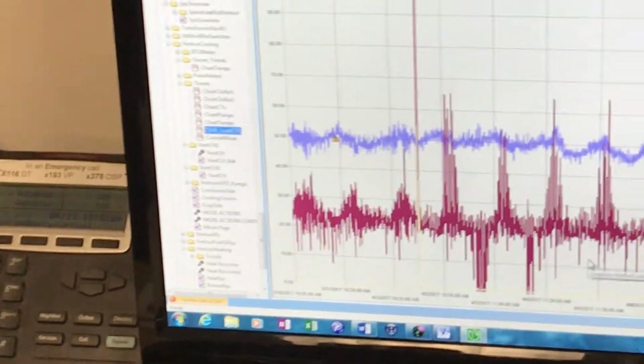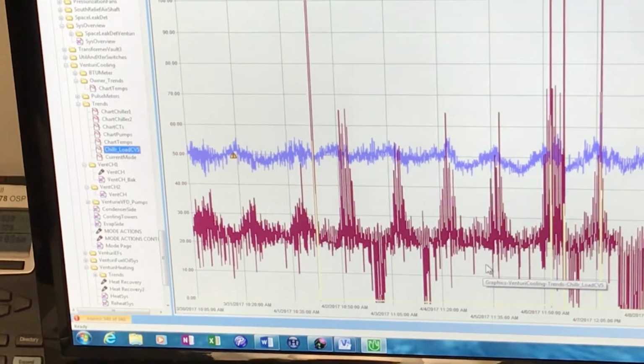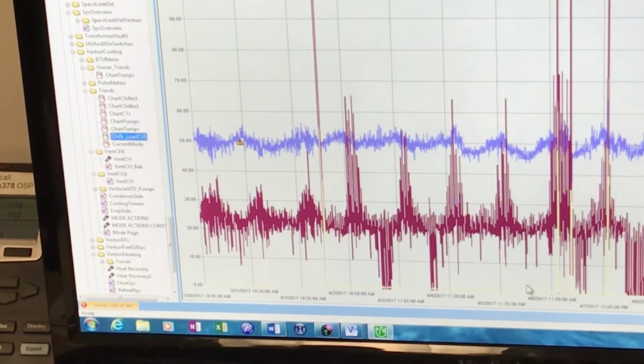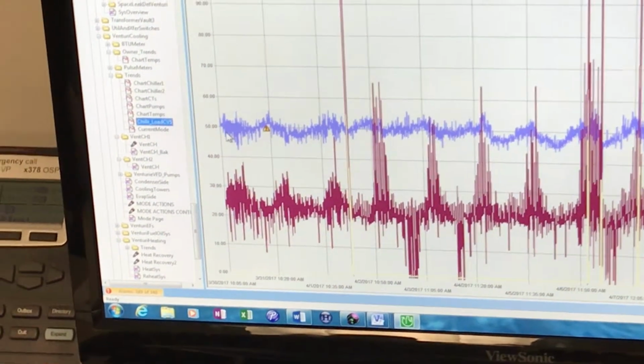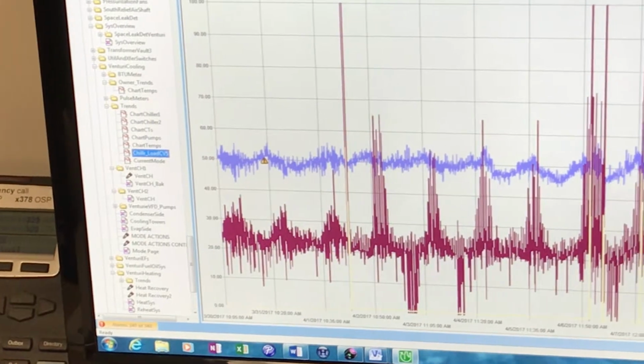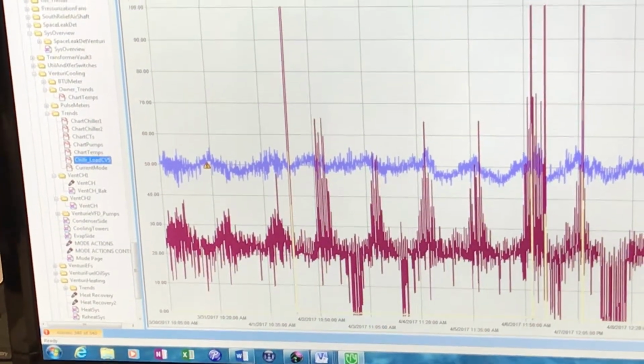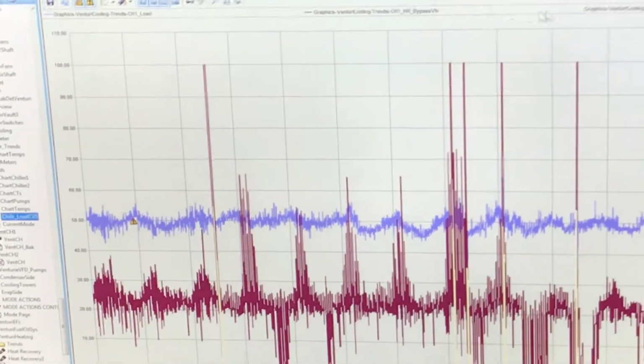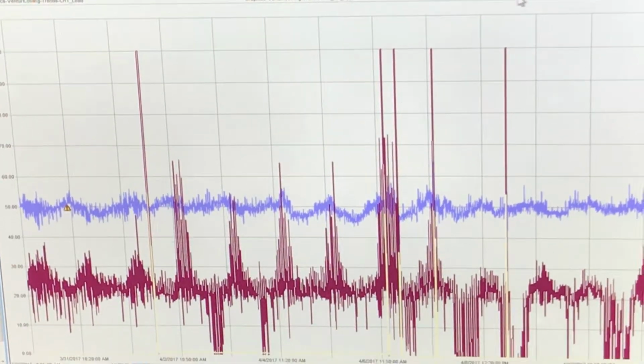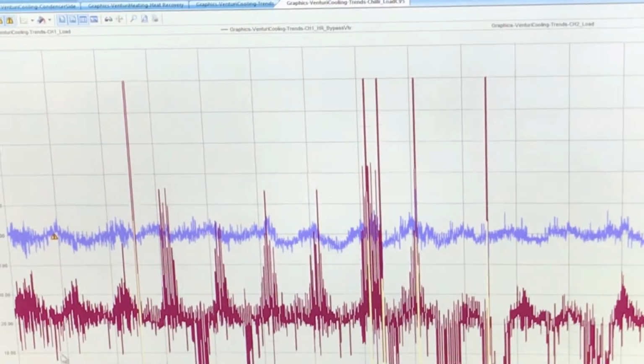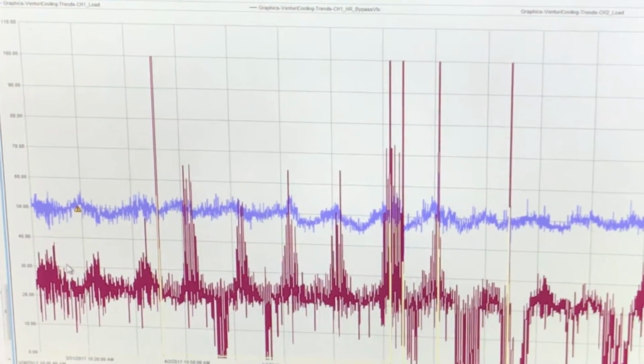So is it normally two for the rotation or three for the rotation? What's the red, what's the blue? The blue is CH1 load. Red's the bypass valve. Okay. And the range for the yellow, chiller load, is what? Ranging between 30 or what?